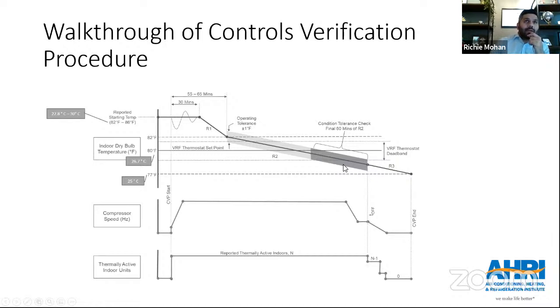That's the data that you're going to use to verify whether the manufacturer's reported or specified compressor speed, which is going to be used for the steady state test, or the other manufacturer-specified values, whether it's compressor speed, outdoor fan speed, or even the expansion valve, are correct. These three specified values that the manufacturer wants to use for the steady state test have to be verified with what you get in this gray area.